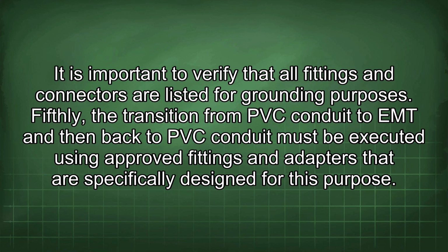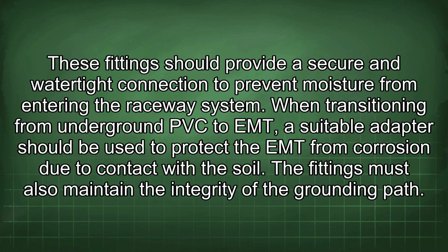Fifthly, the transition from PVC conduit to the EMT and then back to PVC conduit must be executed using approved fittings and adapters that are specifically designed for this purpose. These fittings should provide a secure and watertight connection to prevent moisture from entering the raceway system. When transitioning from underground PVC to EMT, a suitable adapter should be used to protect the EMT from corrosion due to contact with the soil. Fittings must also maintain the integrity of the grounding path.